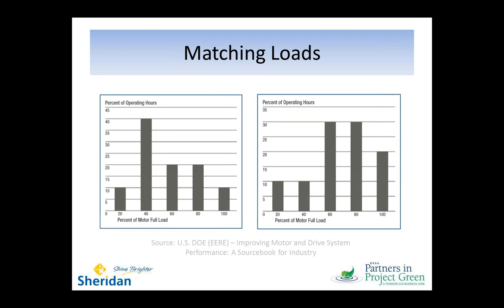The other thing I want to point out here, in the same section of considering the system, is that you really have to think about what the load requirements are. If you're running at one single constant speed, it really wouldn't make a whole lot of sense to invest in a variable speed drive, because you're never varying the speed. I mean, that seems kind of obvious.